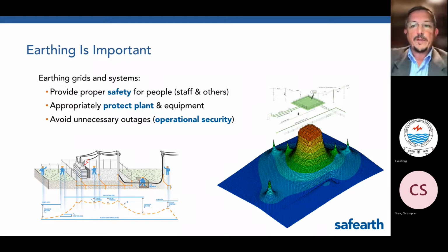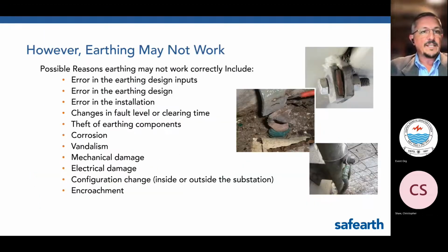But first, let's recall that earth grids and earthing systems are critical assets and that they have three key purposes. They need to keep people safe, they need to protect equipment from damage, and they need to keep the electricity system operating correctly. Perhaps the most important purpose is to keep people safe by limiting step and touch voltages below safety limits, but all of those are important performance requirements of earthing or grounding systems. That's what earthing systems should do, but do they always work the way they should? Did they work properly in the first place when they were first designed and built, or have they changed since? We need to know if they are inadequate so we can make them safe, including repair where that is appropriate.